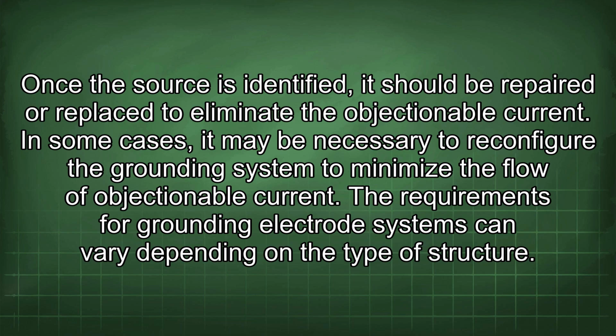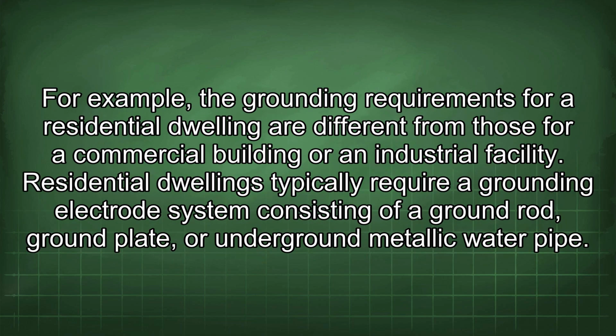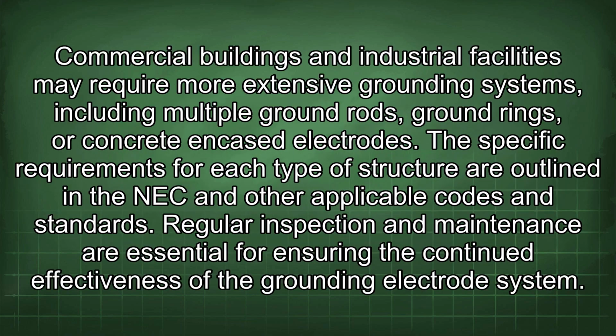The requirements for grounding electrode systems can vary depending on the type of structure. For example, the grounding requirements for a residential dwelling are different from those for a commercial building or an industrial facility. Residential dwellings typically require a grounding electrode system consisting of a ground rod, ground plate, or underground metallic water pipe. Commercial buildings and industrial facilities may require more extensive grounding systems, including multiple ground rods, ground rings, or concrete-encased electrodes. The specific requirements for each type of structure are outlined in the NEC and other applicable codes and standards.